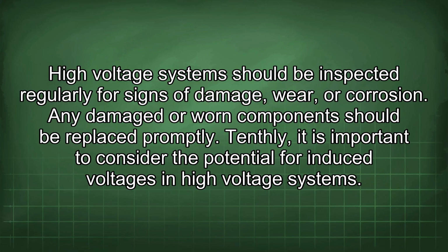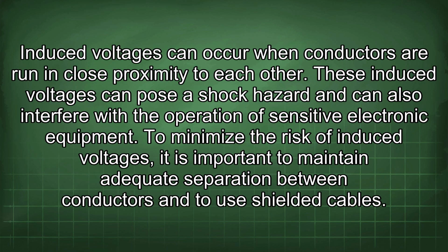Tenthly, it is important to consider the potential for induced voltages in high-voltage systems. Induced voltages can occur when conductors are run in close proximity to each other. These induced voltages can pose a shock hazard and can also interfere with the operation of sensitive electronic equipment. To minimize the risk of induced voltages, it is important to maintain adequate separation between conductors and to use shielded cables.